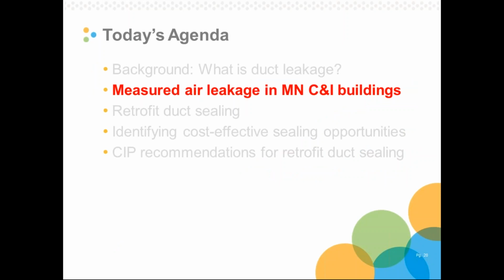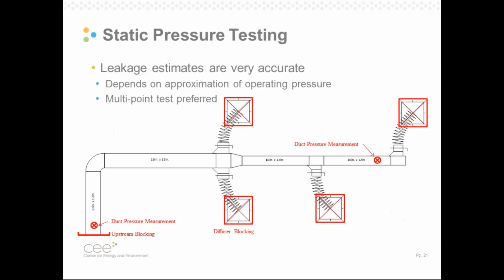So I hope that I've started to convince you that in some cases at least, there is an opportunity for energy savings from leaky ducts. In other words, leaky ducts can cause significant energy penalties. The next step here is to share our experiences in what duct leakage looks like in Minnesota commercial and institutional buildings. And to do this, we did a lot of measurements. Part of this program was to actually investigate measurement techniques for trying to quickly estimate duct leakage in systems.